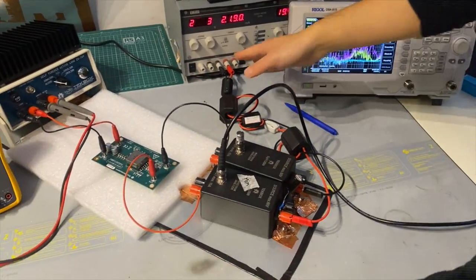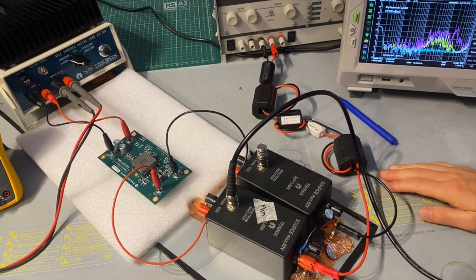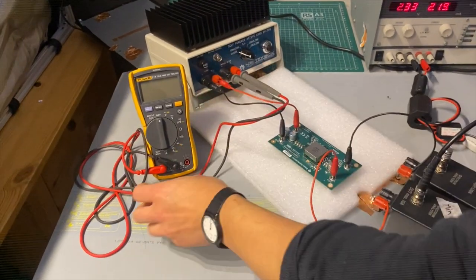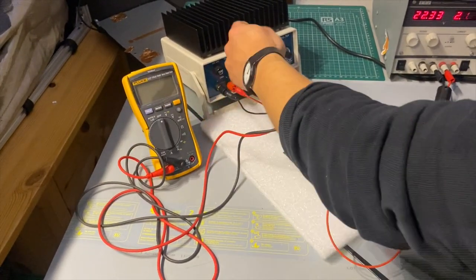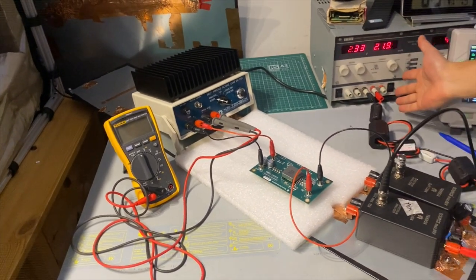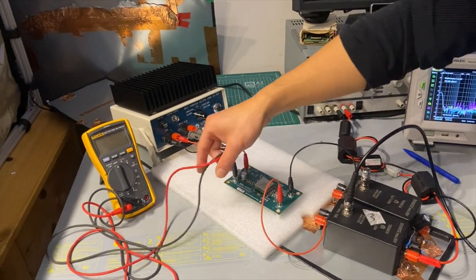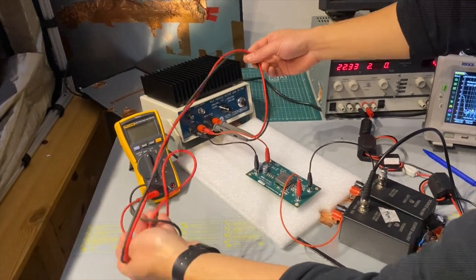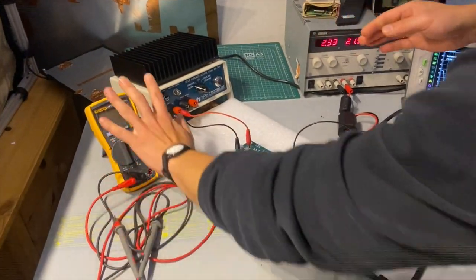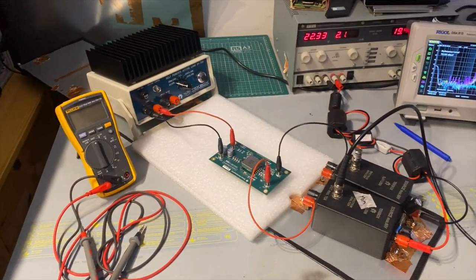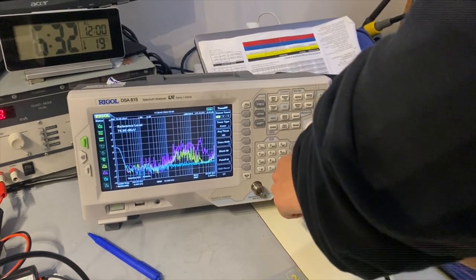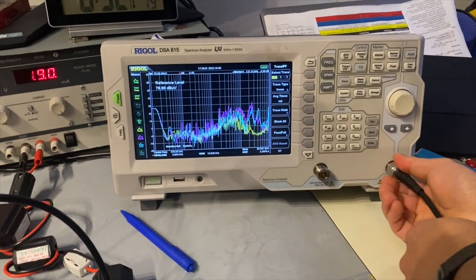So why? Because if you look at the setup, this cable here, we're already protected by putting so many ferrites. Looking at the test setup here, these wires are actually short enough. These wires are also short. But look at here, where we have the meter to really just measure the current going through the unit, even though the fact that this is not actually working. None of this is working, because we're just trying to measure ambience. The power supply unit is not even on. But look at the cables here. This is a much longer cable. So it could be this cable actually acts as a more efficient antenna and causing problems. Well, let's find out if I disconnect this. So now this cable is off the circuit. We still have this configuration. And now let's put it back to see the impact.